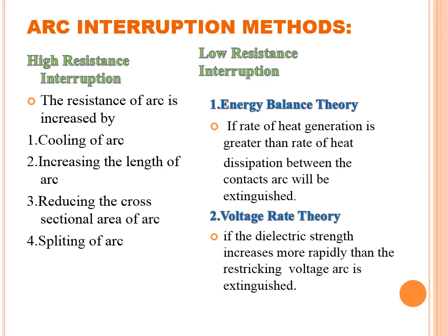The arc must be extinguished or removed as early as possible. There are two main methods: high resistance interruption and low resistance interruption. In the high resistance method, the resistance of the arc is increased so that arc current decreases to such an extent that it cannot be sustained between the two contacts. This can be achieved by cooling of arc, increasing the length of arc, reducing the cross-sectional area of arc, or splitting of arc.